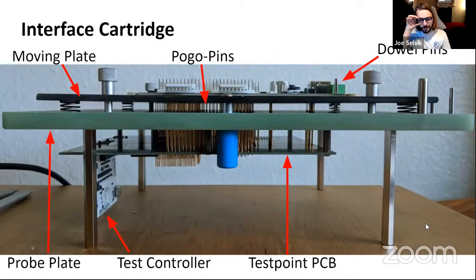So here we have a closer look at that custom cartridge on the right hand side of that slide. In the middle, it all starts with the probe plate, the teal, thicker colored plate, and this is the first piece that gets CNC machined so you can insert all of your probes. What goes inside first is the receptacle, a metal sheath that each probe is inserted into, and on the bottom is the test point carrier board, which receives each of those receptacles and routes those signals to the various instrumentation.